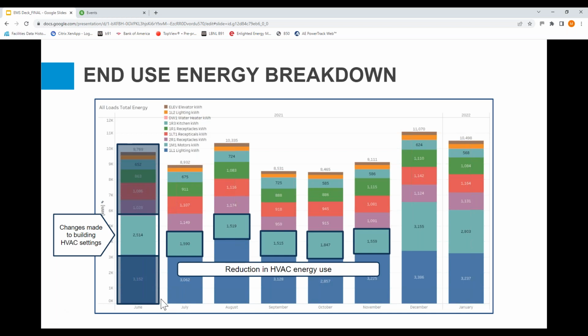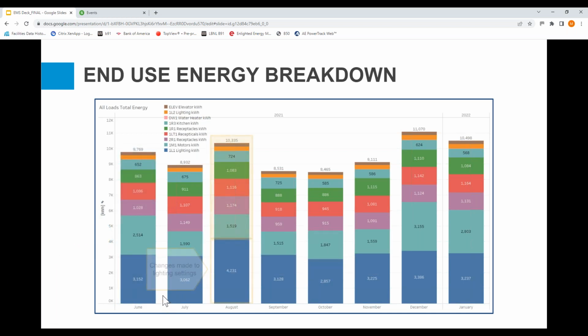Another thing we did was on the lighting side. Lighting ended up being the largest category of energy use for this library, which makes sense since there's a lot of lights. What we found was that the light levels had just been generically set at about 90% of their output throughout the entire library.